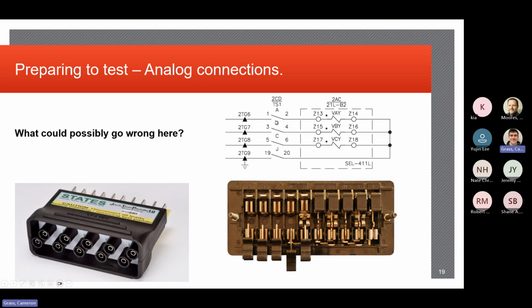Basically be supplying voltage to everything but the relay on the rest of the circuit, which could end up having a couple scenarios. Number one, somebody could be working on that circuit, and adjacent to it, somebody else, like an electrician in another panel that could be paralleled to this circuit, could get zapped with the test set voltage. Could be supplying secondary voltage back up to a PT. That creates a lot of issues, not even necessarily safety issues, but could damage the equipment, whatever it may be.